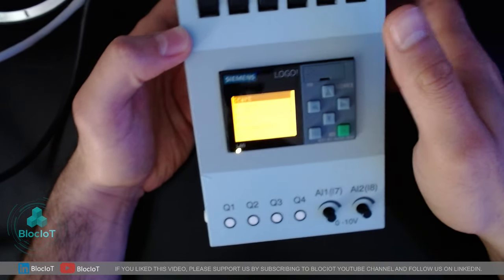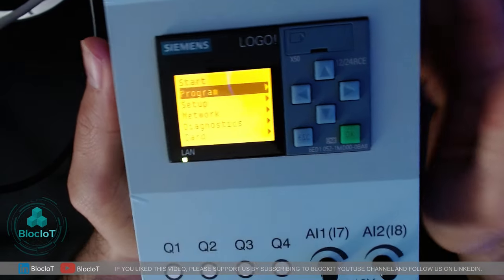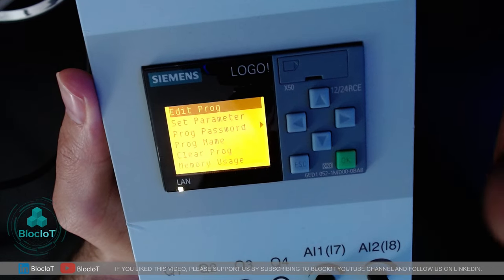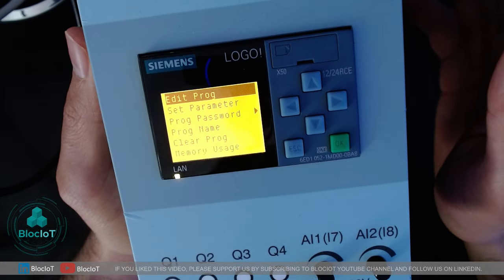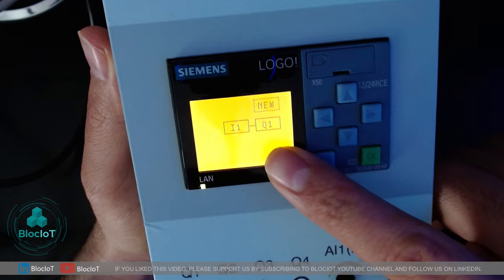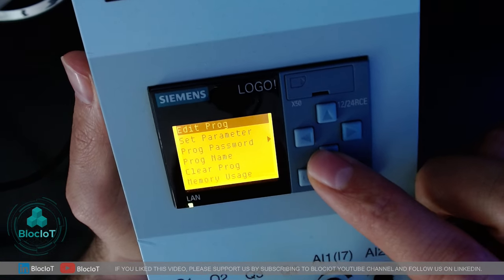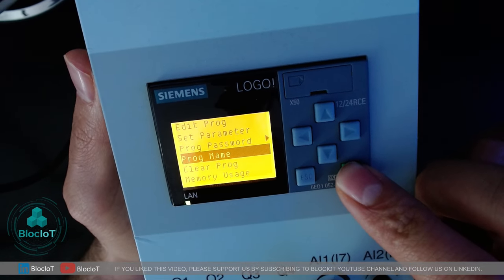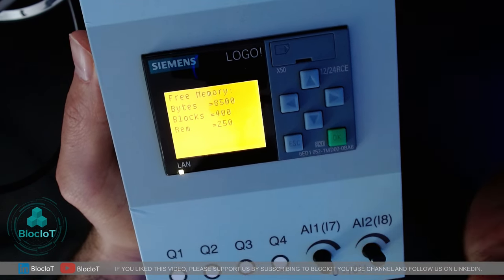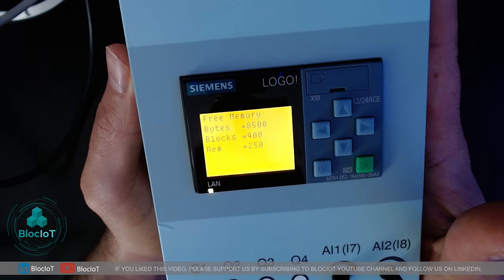The second option is very neat and unique to Logo — I don't know of any other micro-PLC that gives you this option. You can go to the program menu and edit your program directly on the device, without using the software. If you are patient enough, you can write a program using just the keypad on the Logo. You can edit the program, set different parameters, change the program name, clear the program, and browse memory usage — for example, this Logo model supports 8500 bytes, 400 blocks, and 250 retentive memory slots.